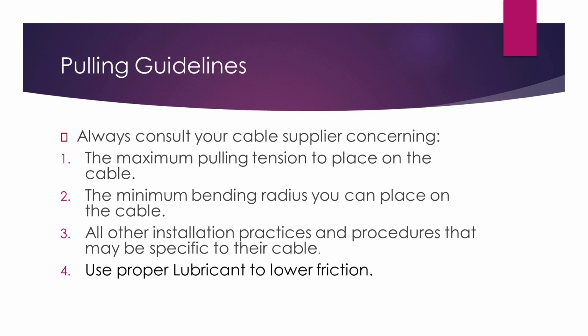So when you're talking about pulling wire, you need to talk to your cable supplier, Okonite, whoever y'all buy from. Just know there's a maximum pulling tension on this stuff. You've got your dynamometers out there, and you know how many foot-pounds or kilonewtons you're pulling on this stuff. Minimum bend radius also matters.